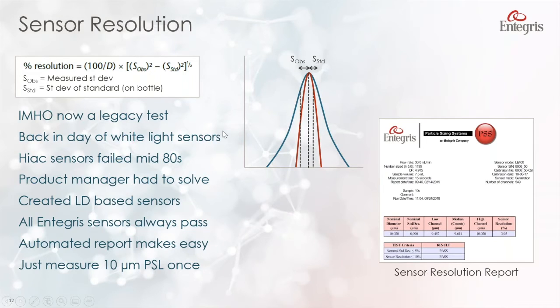In my humble opinion, I don't know why this is still in here. Back in the 80s, when I was doing this at another company, we were actually using white light sensors, and some of these failed. But as soon as the industry switched over to using laser diode sensors, certainly I've never seen a sensor created by Entegris that has not passed this. But I recently wrote an email to USP to explain this to them, and they told me, yeah, go away. So I don't see this test disappearing anytime soon.